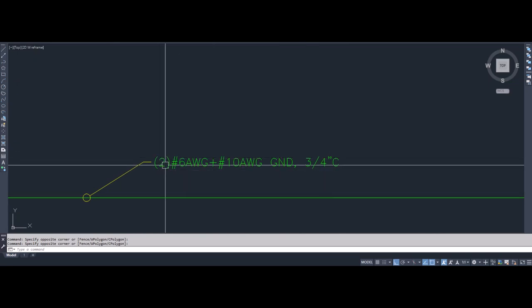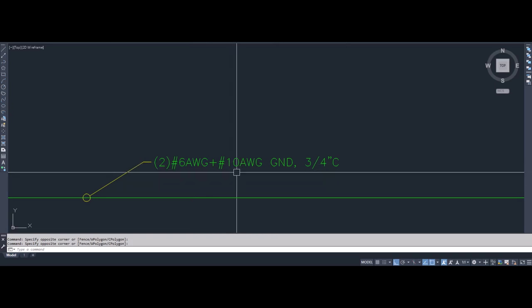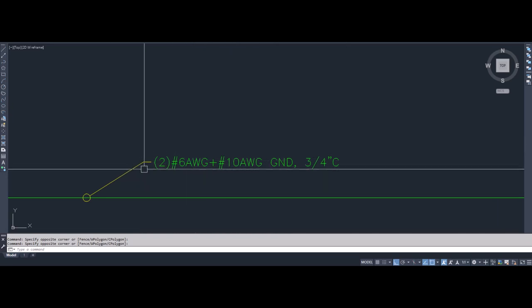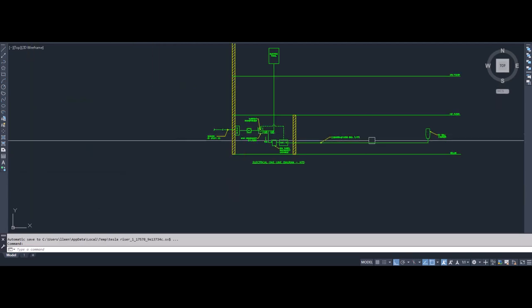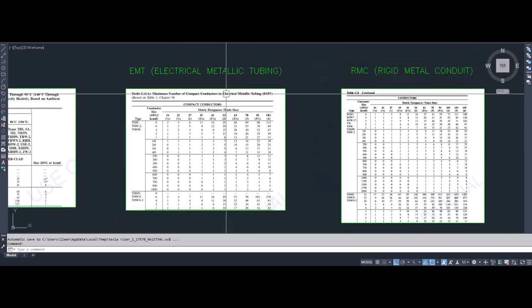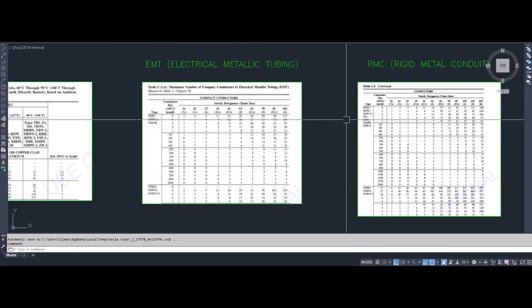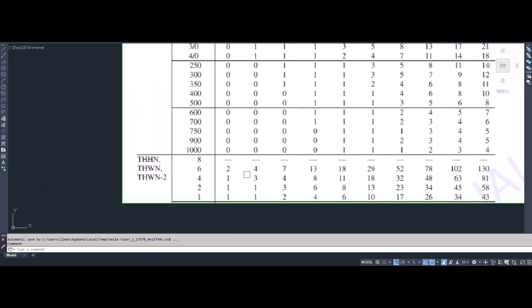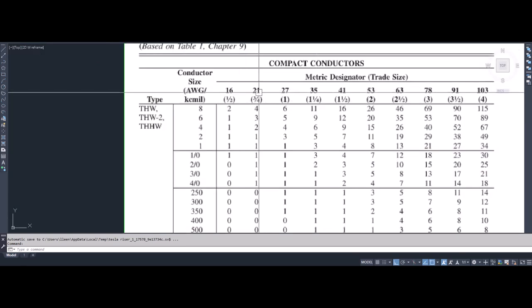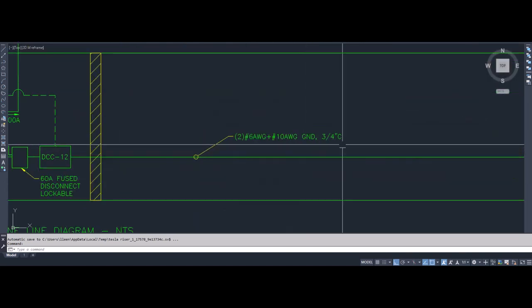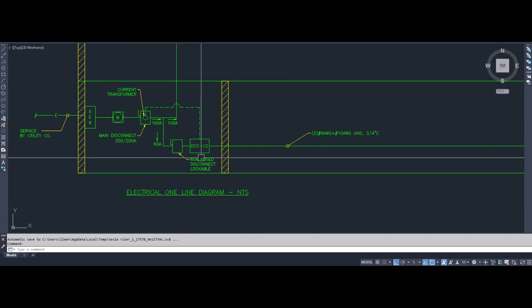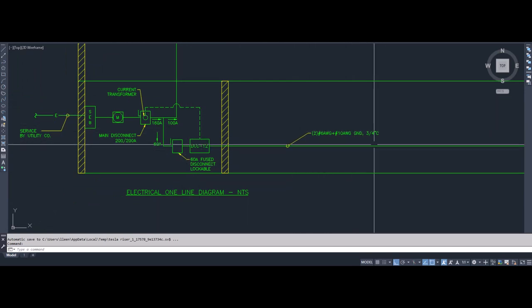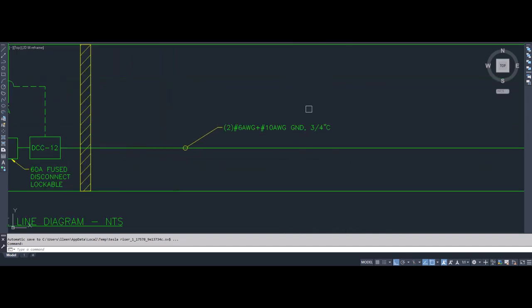So there's going to be two number 6 and one number 10. The 6 is larger, so I'm just going to assume that we have 3 number 6s. When you go to this table to size the conduit, there are 2 charts, one for EMT tubing and one for RMC. Generally, they're about the same, but I put them both here so you could compare. For number 6, 3 of them would fall under here, up to 4 conductors, and that's a 3/4 inch size. So for this 60 amp, you need something like this, okay? And this is generally what you should see installed.